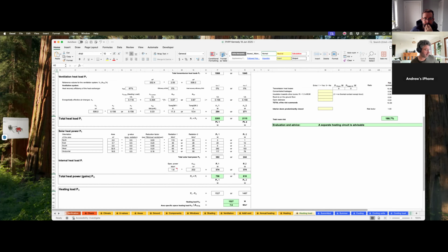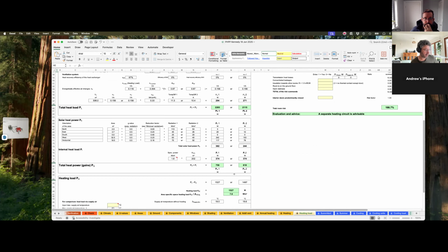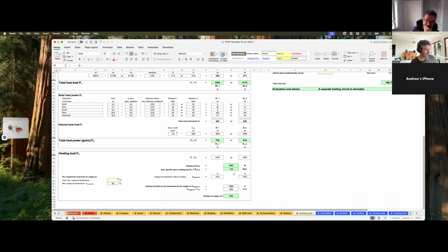They always have to balance, don't they, too? Yes, they have to balance. Be the same. So this figure here, 1527 watts, 1.5 kilowatts. In theory, that's how much heating you will need. So the smallest air conditioning unit. However, as we've been discussing, when we've got a multi-story house, it's not going to spread around. So we at least need a unit upstairs and downstairs.